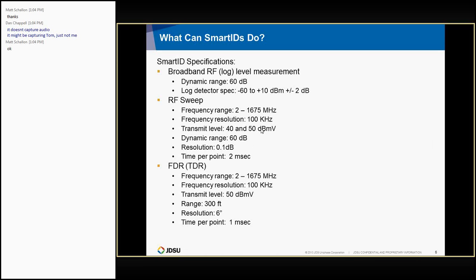Okay, I think on the receive side, the dynamic range is 60 dB. On the transmit side, this shouldn't be in there. I have to apologize for these goof-ups. I'm just seeing them right now. And the transmitter for the FDR works essentially the same, has the same specs. The TDR that's derived from the FDR will go out beyond 300 feet with a resolution. It's spec'd at 6 inches, but it's probably closer to a foot in actual practice.